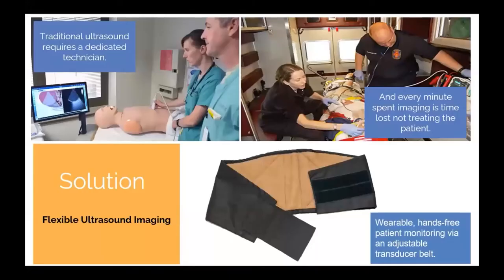And that's what we plan to do. Flexible wearable ultrasound imaging is a massive leap forward in the medical toolkit, not only in trauma transport, but in the hospital and beyond. This technology utilizes ultrasound signals passed between elements of an array to identify its shape and produce a coherent image. This allows the transducer to adhere to and flex with the skin and the body as it moves. We currently envision a belt or strap, not unlike a blood pressure cuff, that EMTs and physicians can apply to the body and leave attached.